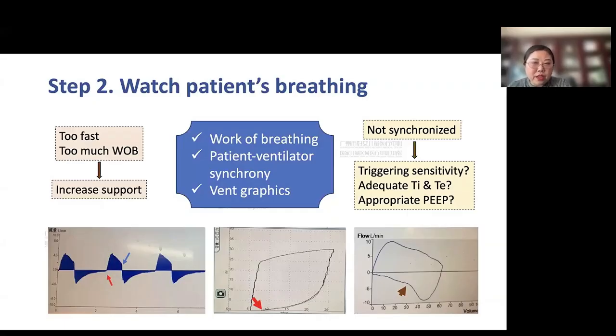You can have the triggering sensitivity set wrong. You may not have adequate TI or TE, or your PEEP may not be adequate. So really you have to watch this baby. A lot of people just watch from far. Okay, they don't touch the baby. They watch from far, they look at the ventilator, and the ventilator looks like it's giving breaths regularly.